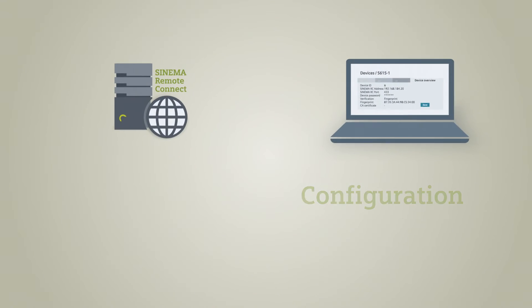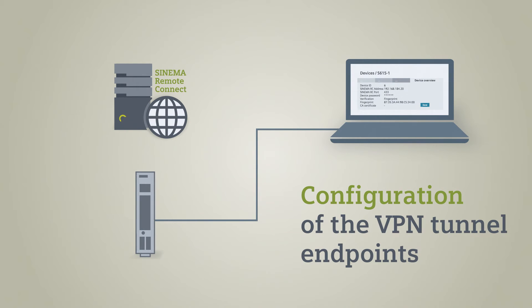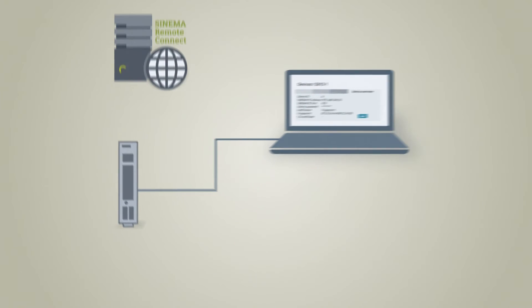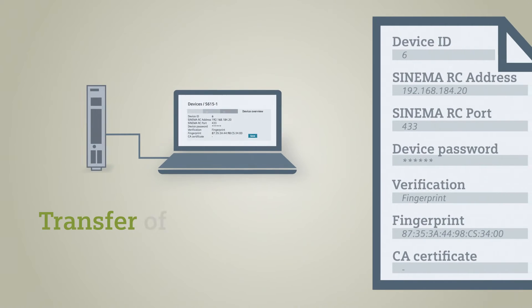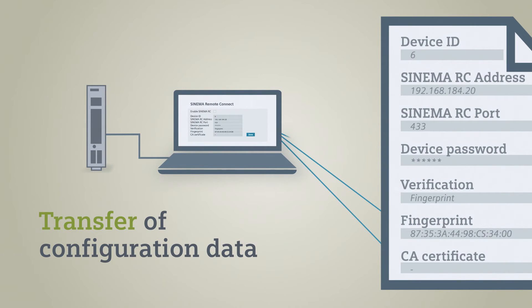In our example, this tunnel endpoint is a SCALANCE S615 security module to which the configuration data is now transferred. This is performed conveniently via auto-configuration with only a few parameters.